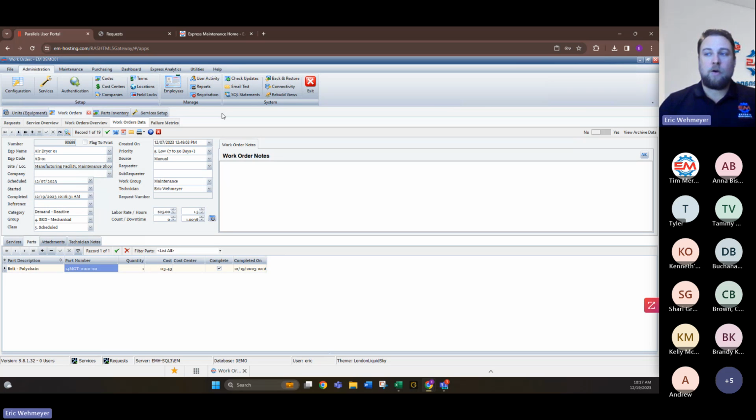order. Now, you have service history that shows labor cost, parts cost. You have data like the time that it was scheduled versus the time it got completed. And so now you can capture information like mean time between failure, mean time to repair, total cost to maintain. And all of these KPIs, these performance indicators are helpful when trying to figure out how do we justify hiring more people next year?